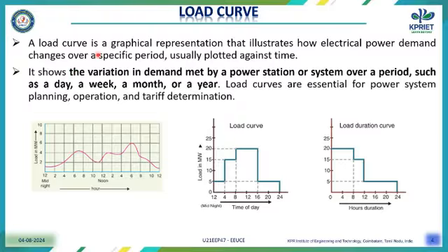What is a load curve? A load curve is a graphical representation that illustrates how electrical power demand changes over a specific period, usually plotted against time. So this first diagram represents the basic load curve. The x-axis represents the time for a period of 24 hours. The y-axis represents the power demand changes, that is, load in megawatts. For each and every hour, what is the load in megawatts? That representation is nothing but the load curve.